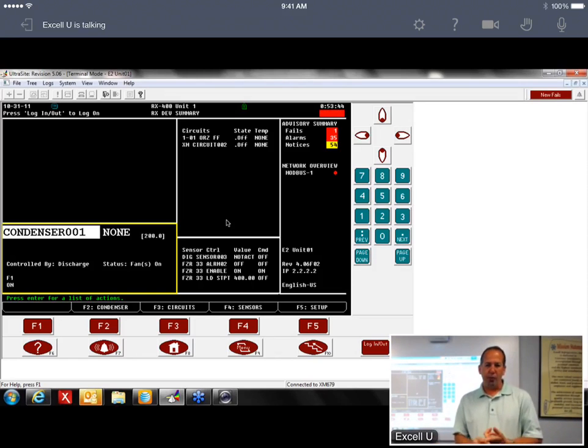But if you're on a new store or a remodel, and you have your network up, with all your network already run to the XM controllers, you can dump all the parameters into it from the E2, and that's the way I suggest doing it. So if you're on a remodel doing a couple cases a night, I'd push your coordinators hard to have the network up and running, or at least available, so when you put these cases on you've got the network there and can talk to them over the E2. It's a lot simpler to talk to that device through the E2, so having that network there is crucial.